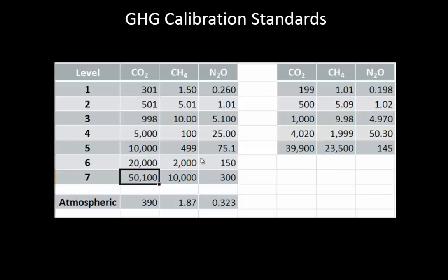So this is our second set of calibration standards. We were running 5 levels. We now run 7 levels. As we go on, we get a better handle on the range of concentrations we experience. Of course, most of those samples are low-level samples, but the high-level ones you need to be able to accurately measure as well.